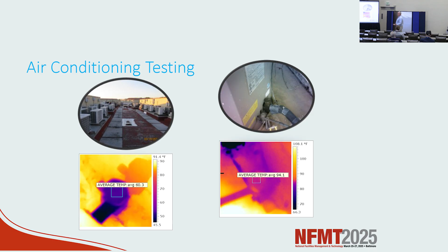Going around liquid and gas lines, they tell you we want to see a 20-degree delta between the liquid and gas, and a 20-degree delta between the inside and outside. Many times we have failures because of convective loss, or a system that's not charged properly. So there might be other tools needed to identify that.